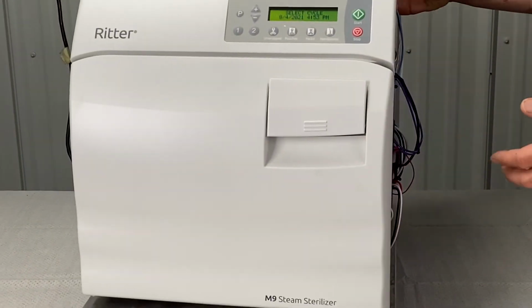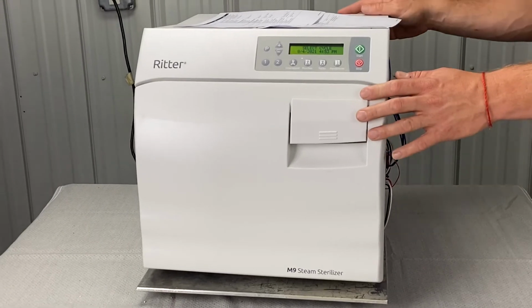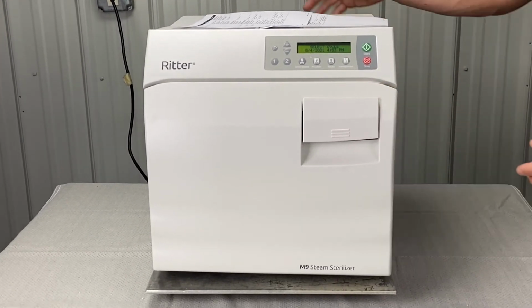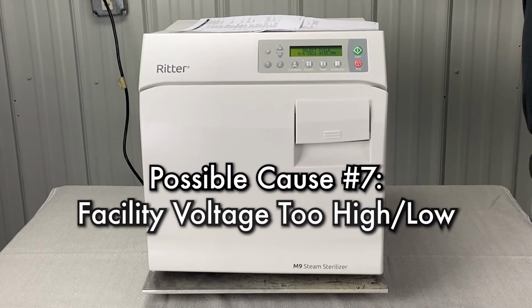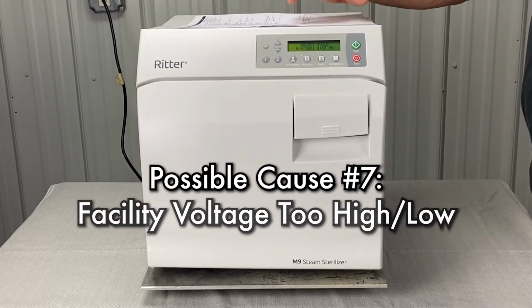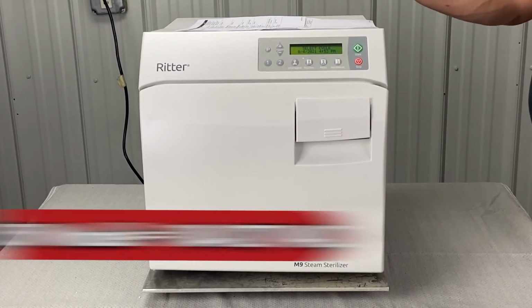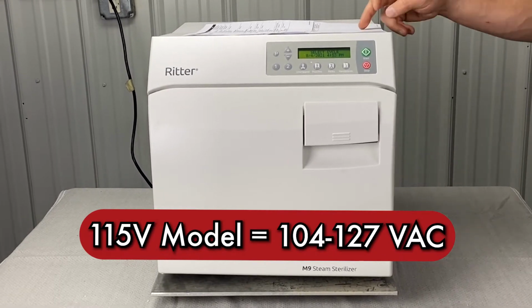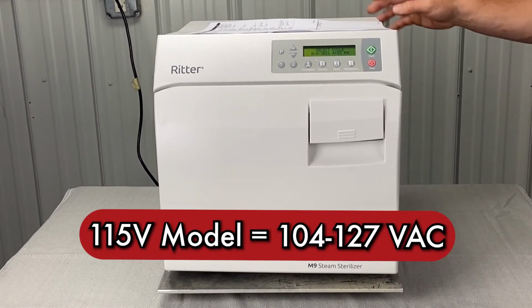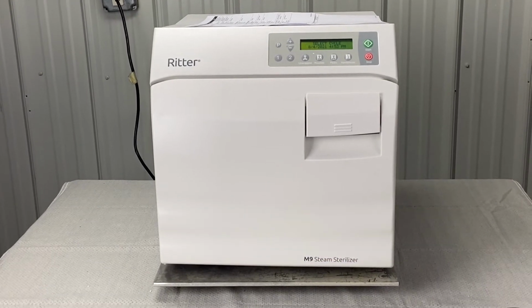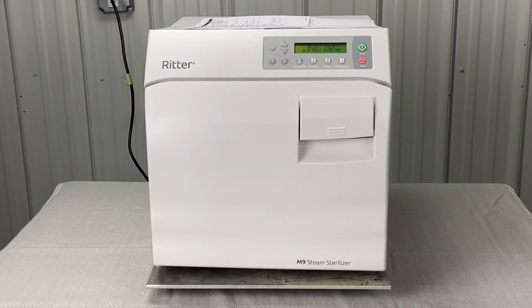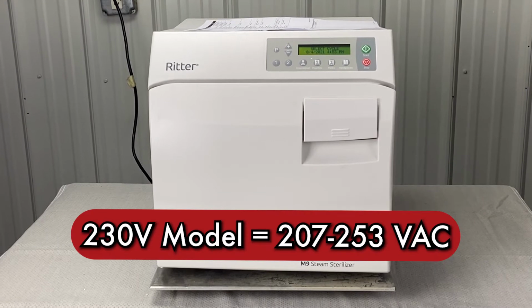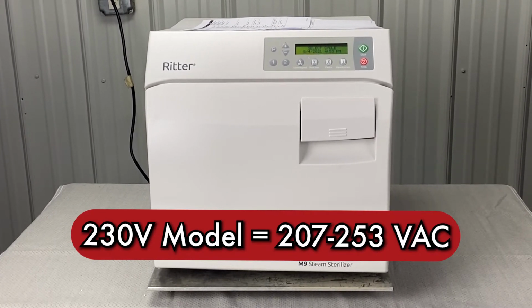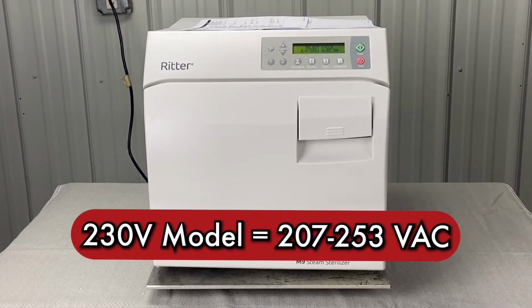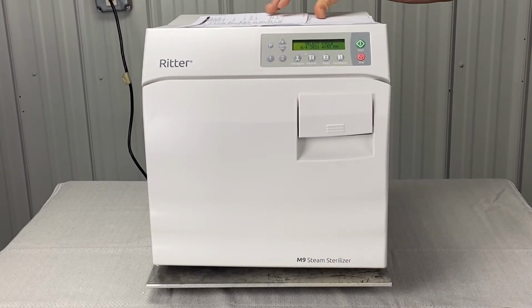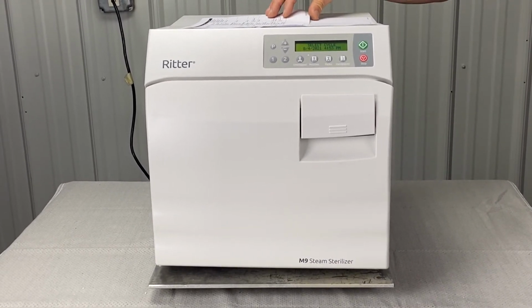So loose or damaged wiring we talked about, gaskets we talked about. It could be your facility voltage. The voltage on the wall for a 115 volt model should be 104 volts AC to 127 volts AC. You can test that with a multimeter. We can talk you through that. If it's a 230 volt model, it needs to be between 207 and 253 volts AC. Could be those.